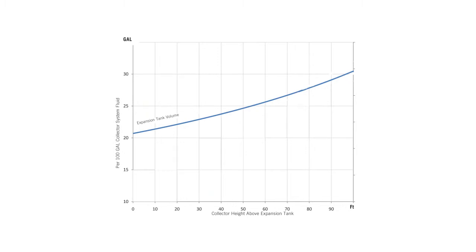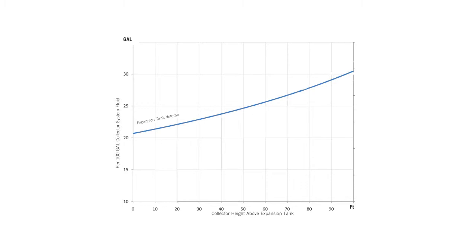This chart, also found in the Heliodyne HCOM Manual, can be used to help determine expansion tank size. For example, if the collectors are 50 feet above the expansion tank, then the expansion tank should be sized to allow 25 gallons for every 100 gallons of total system volume, or 25 percent. This chart will also be used in the installation process to help determine initial fill pressure according to collector height and fluid temperature. For systems with height differences greater than 100 feet, please contact Heliodyne or your solar design engineer for further guidance.